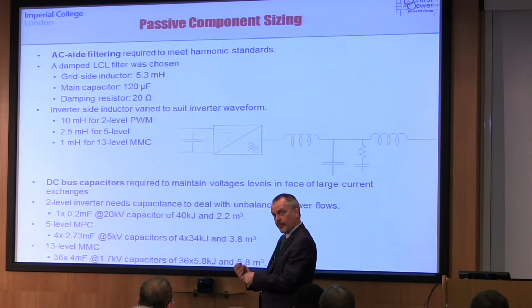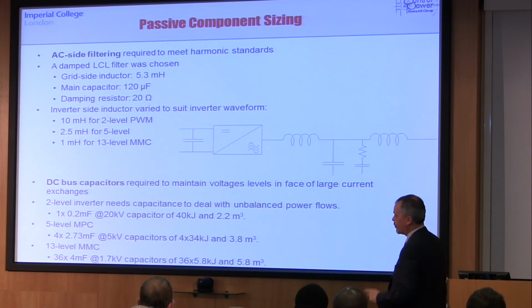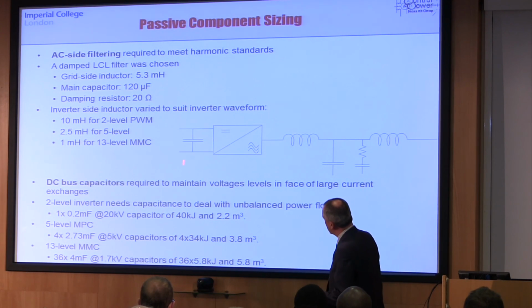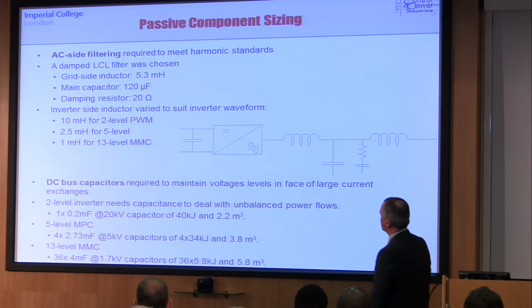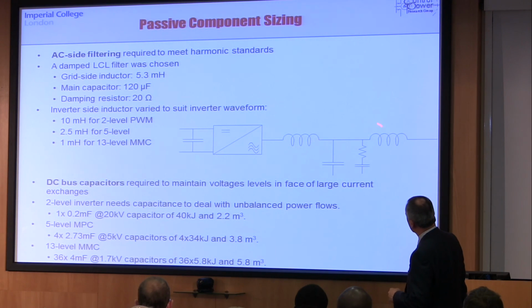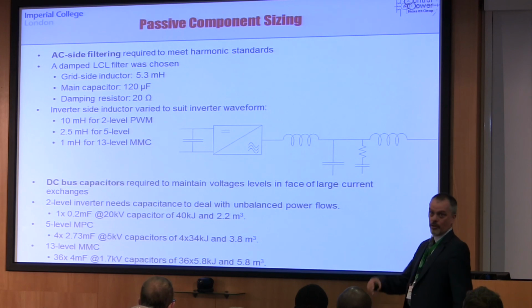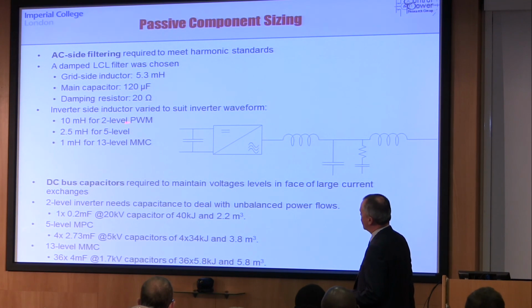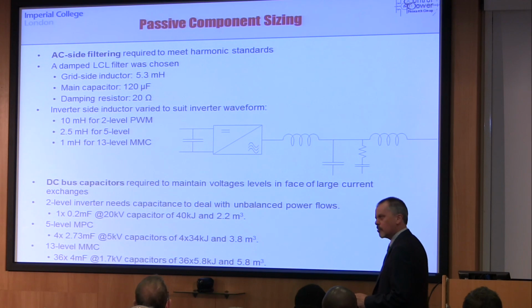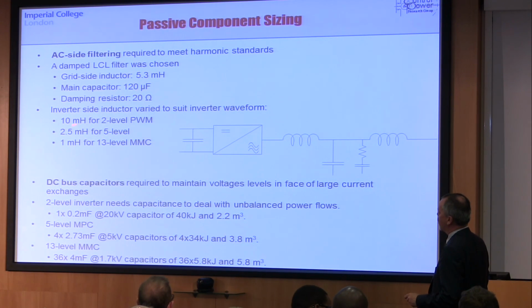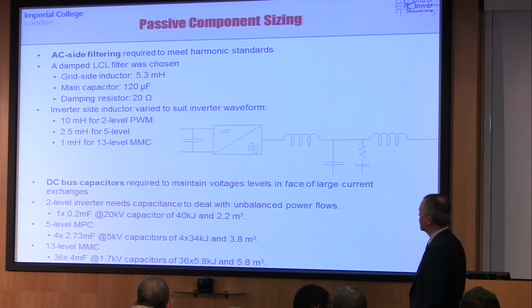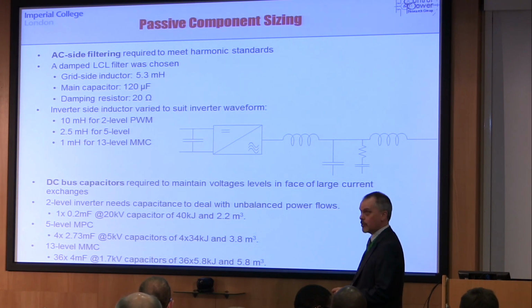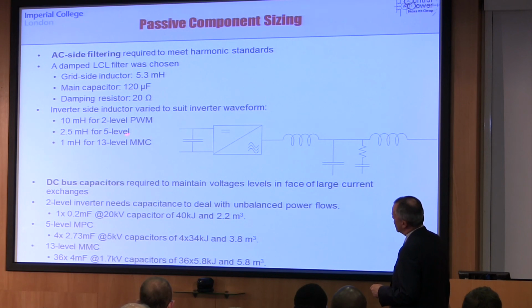We compared them on filter use, so we've got to think about the AC side filter for harmonic purposes, and we've got to think about the DC side capacitance to support the voltages of the multi-level in particular. So we looked at a filter design and changed that filter as the quality of the waveforms changed. And what we saw was for 2-level PWM at about 2 kilohertz, I think it was, we needed a 10 millihenry inductor, but that could shrink by a factor of 10, at least in inductance, and probably therefore in volume, by going to multi-level, or a high number of levels. But interesting, though, on big-scale MMC, you can dispense with the filter. At these sorts of level numbers, you still need a filter of some sort.